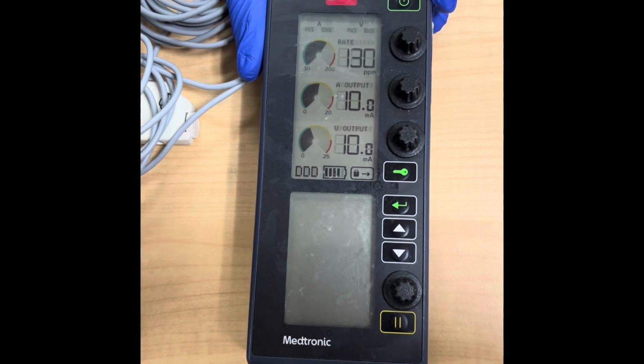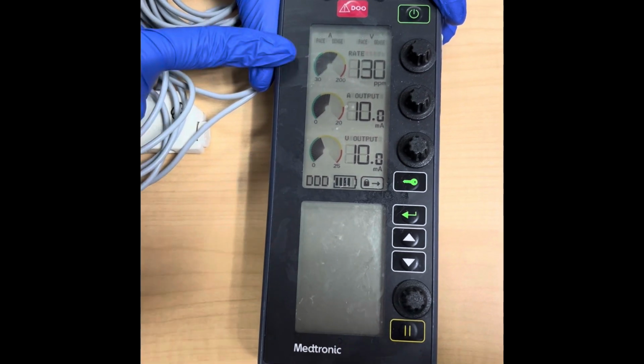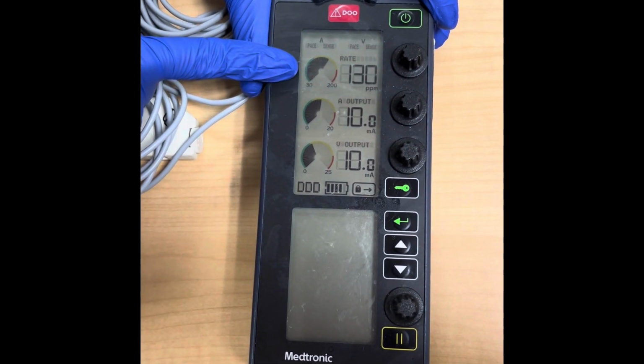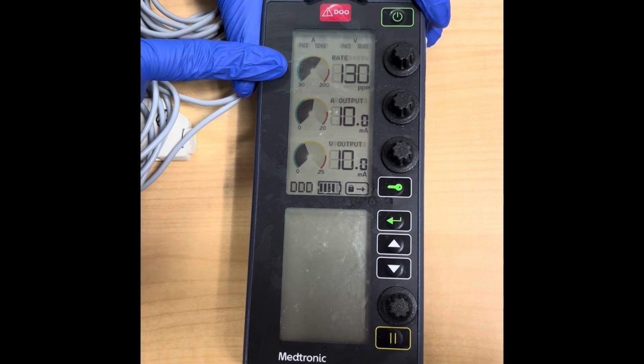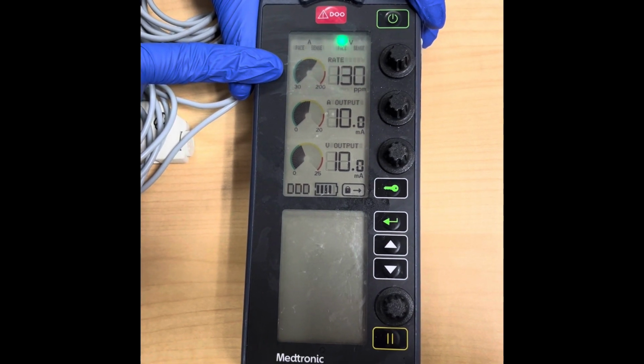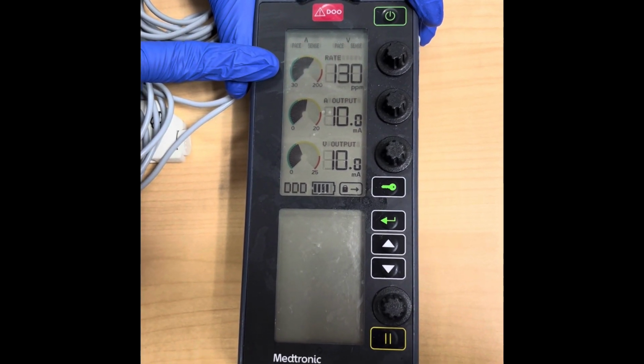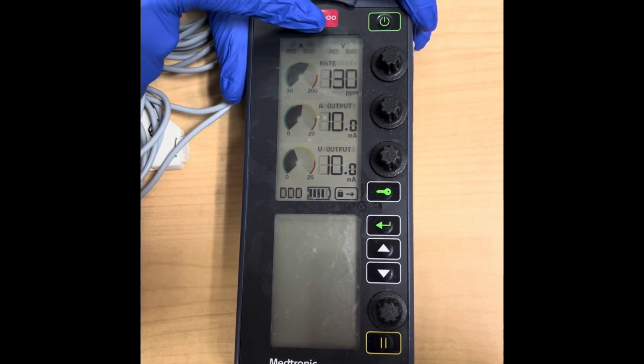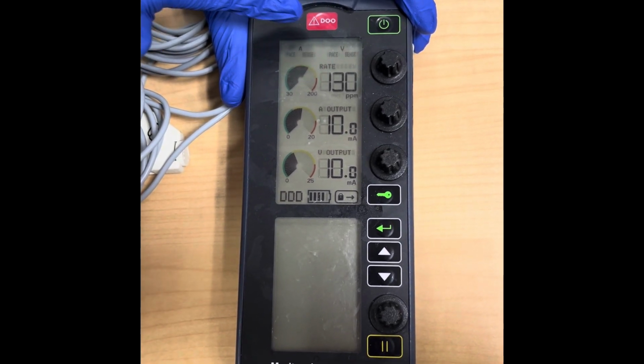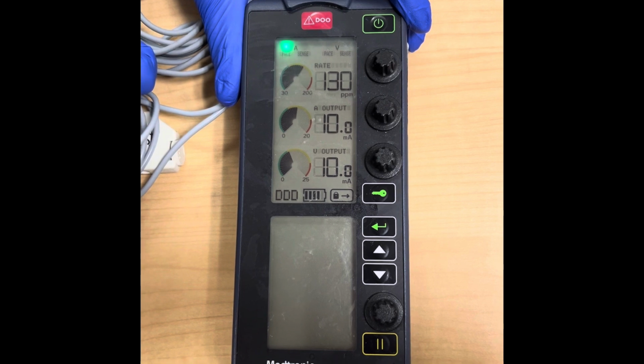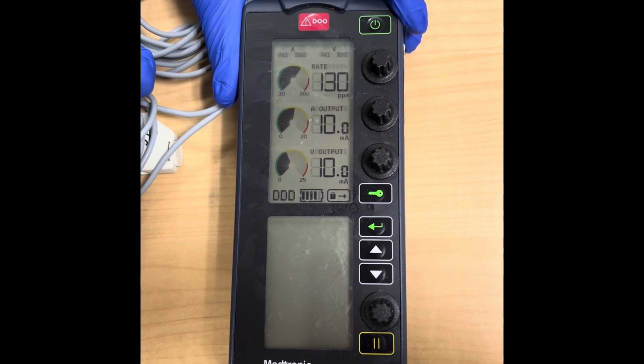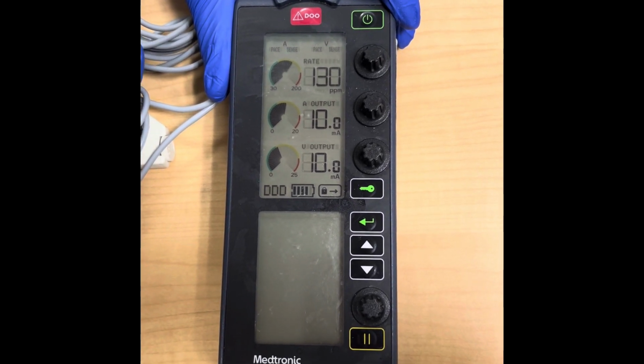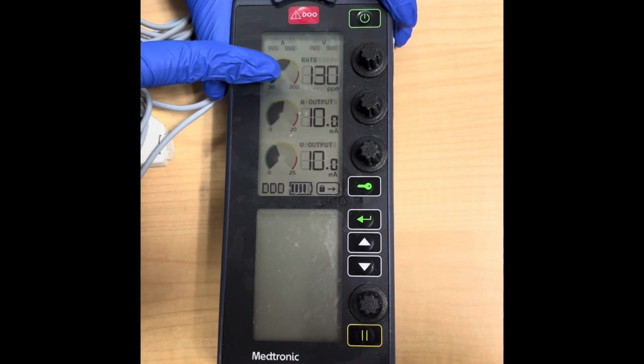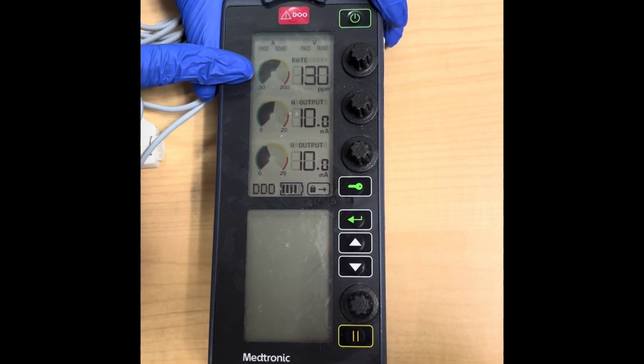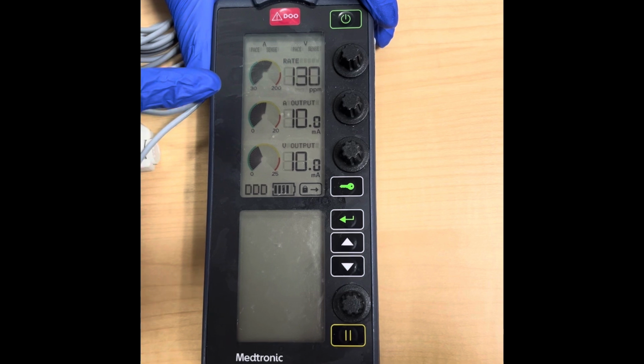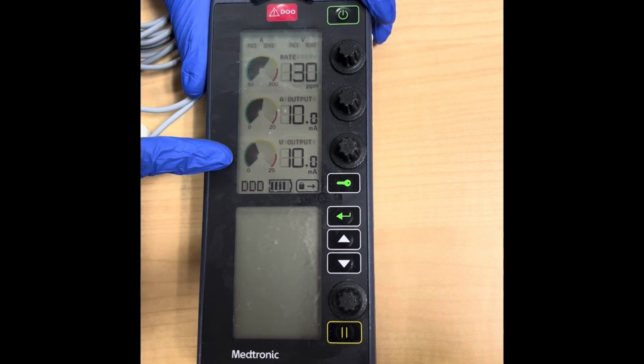So as you can see, this pacemaker is set to pace both atrium and ventricle. So at the top you have an A with a green flashing light and a V with a green flashing light. That's telling us that the pacemaker is pacing both atrium and ventricle. If that flashing light was yellow, that means the patient is being currently sensed. The next setting you have is the rate. So we are currently set at a rate of 130. And then we have atrial and ventricular output, and those are both set at 10.